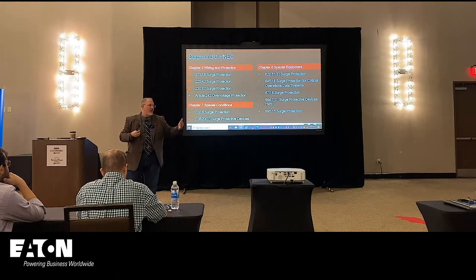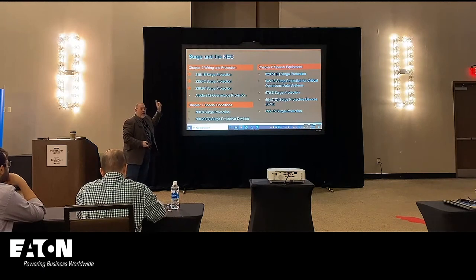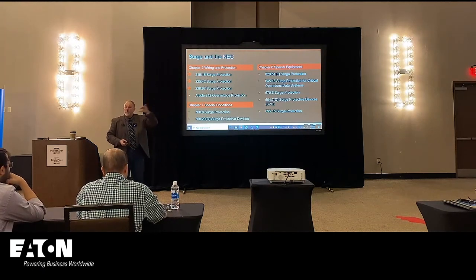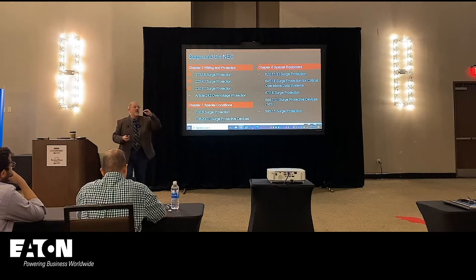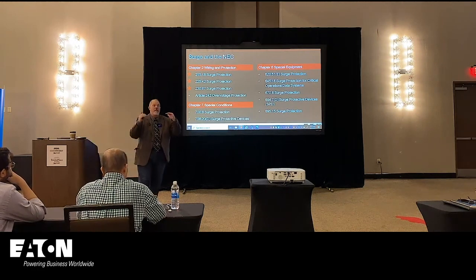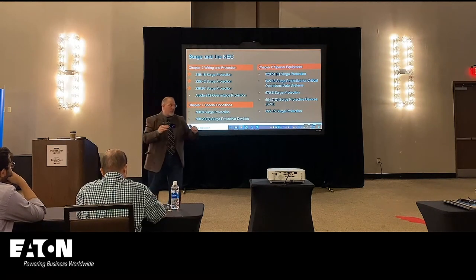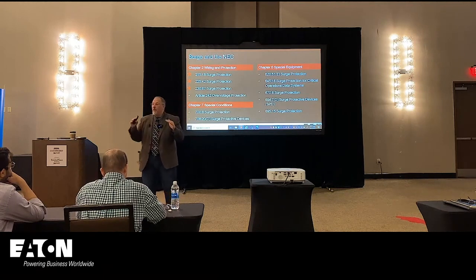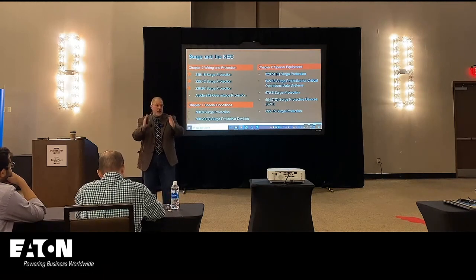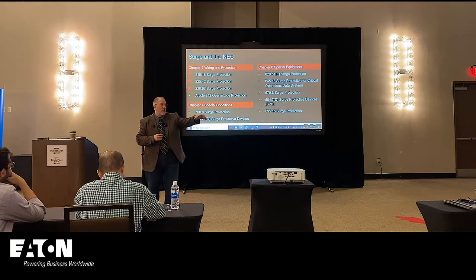And then we said, well, we can't make it required in both locations. So we modified it and added some language in 215 and in 225 that recognizes those applications. And I guess the bottom line with surge, from an industrial and a commercial, regardless of application, is you want those lead lengths very, very short, and you want the surge as close to the structure as possible in your distribution.